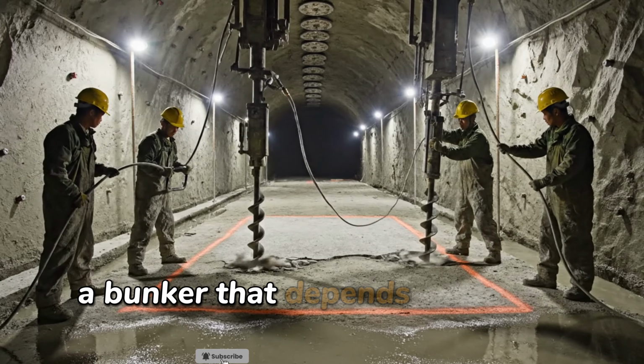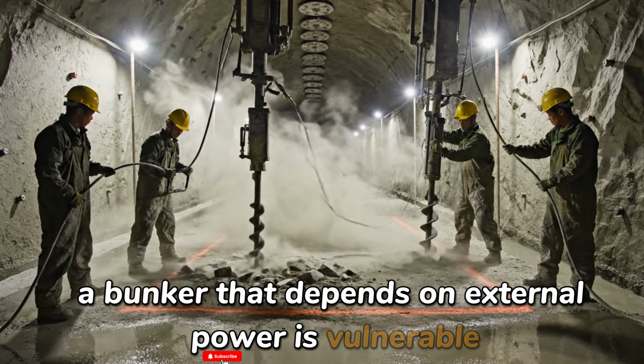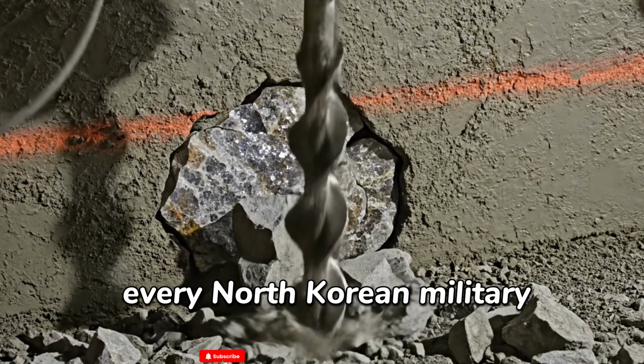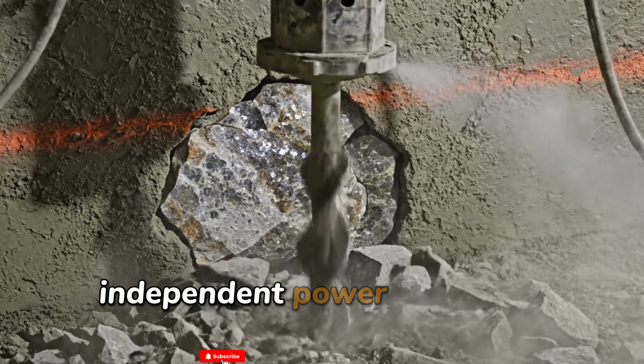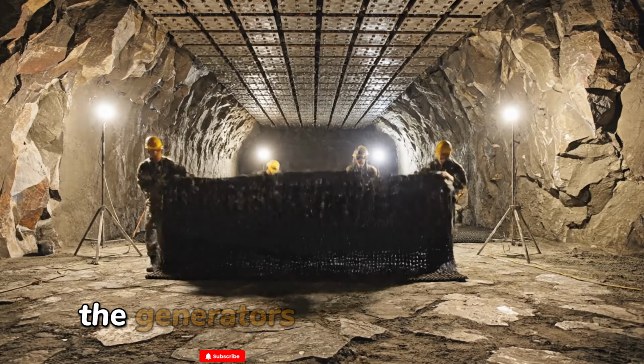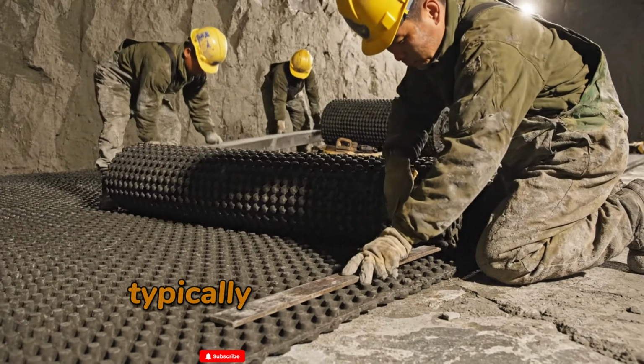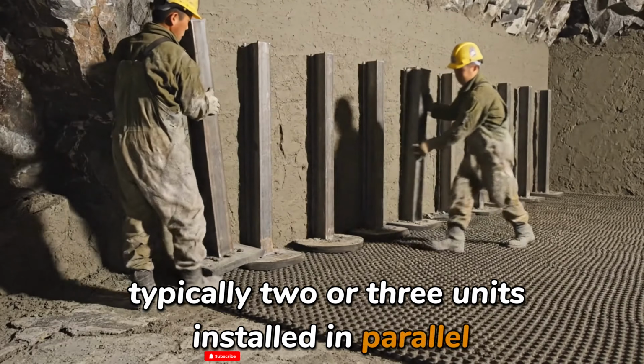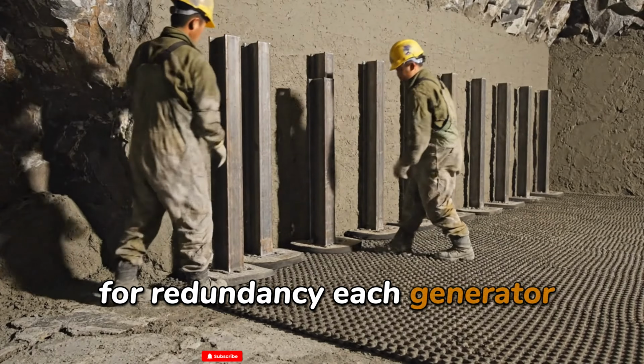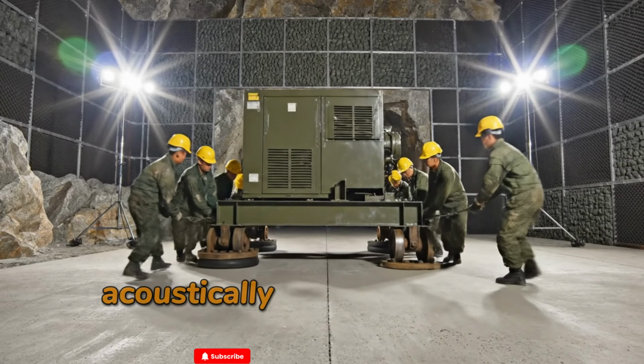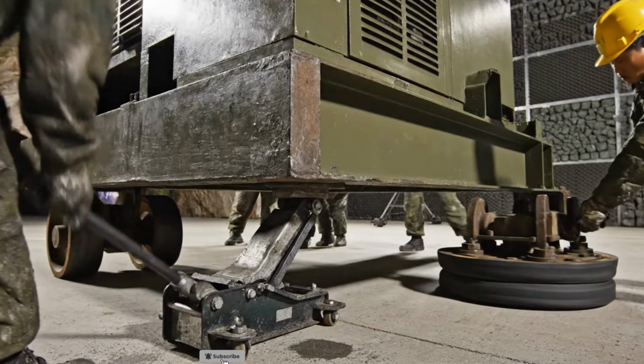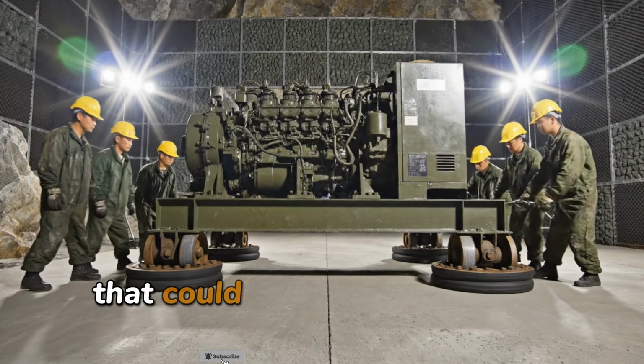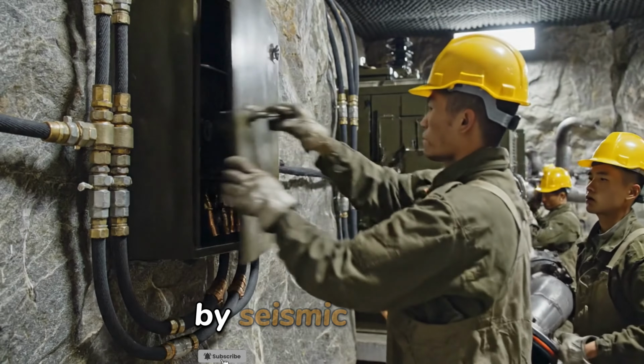A bunker that depends on external power is vulnerable. Every North Korean military bunker has its own independent power generation system. The generators are diesel-powered, typically 2 or 3 units installed in parallel for redundancy. Each generator unit is housed in its own acoustically isolated generator room, a chamber within a chamber, to reduce the acoustic signature that could be detected from the surface by seismic sensors.